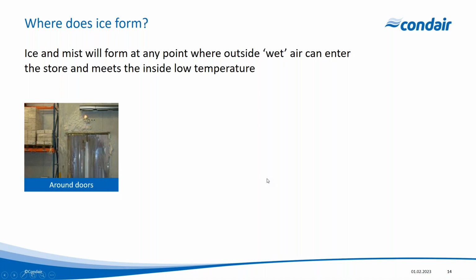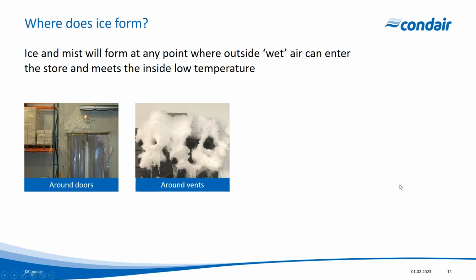It could be interfering with lighting. It could be interfering with exit signs or safety signs. And certainly affecting the efficiency of that strip curtain. It could be around a vent. If we've got air being poured into a cold store from a vent, then we can get ice forming around that vent as that moist warm air comes into the cold room and it immediately hits that colder temperature and the moisture starts to freeze.